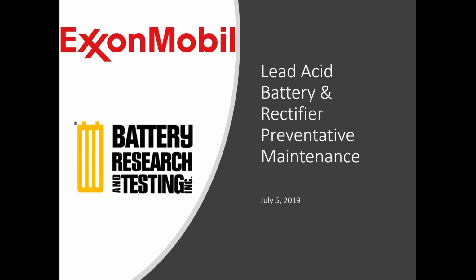From having performed load tests on thousands of cells, I can tell you when you go in, float voltage has no indication of, or very, very limited indication of, the health of the battery, whether it's floating a little bit high or a little bit low, even outside the recommended window. Very little correlation to how that battery or that individual cell can perform under load, or even the life of it. Right, not as much as the impedance, right?